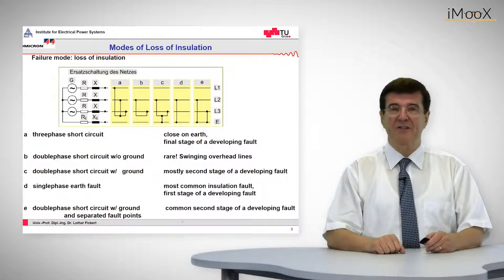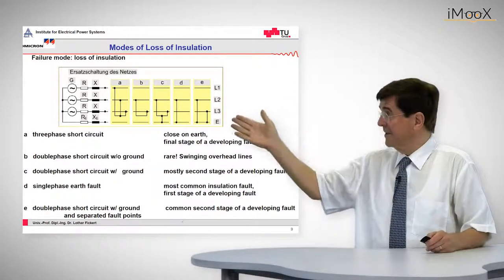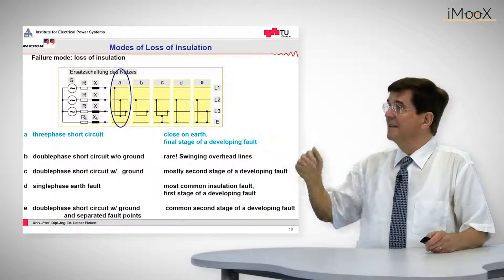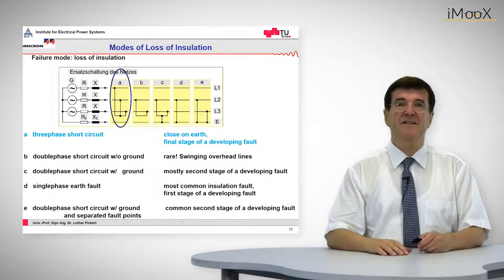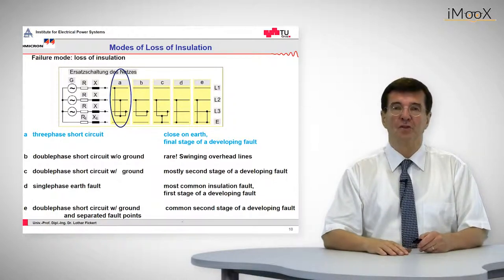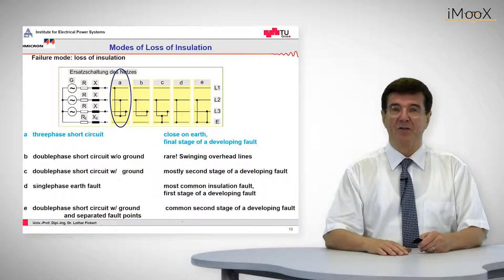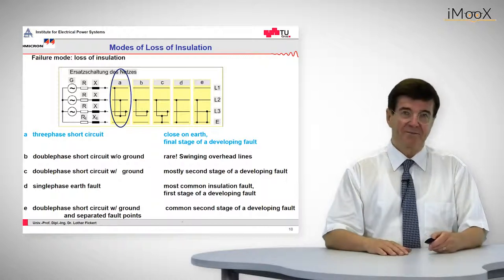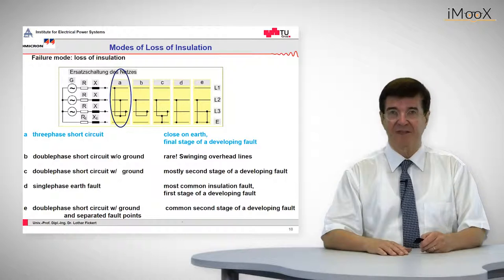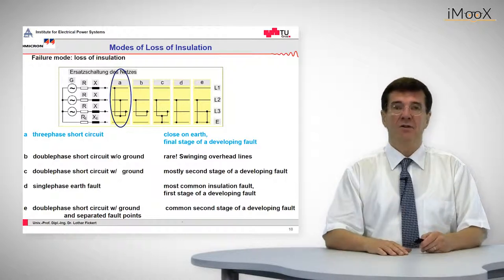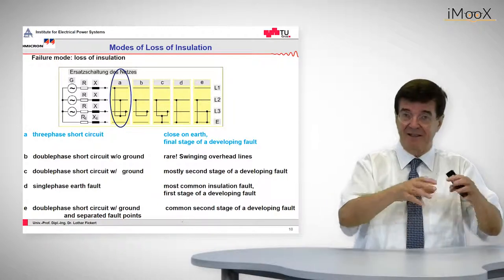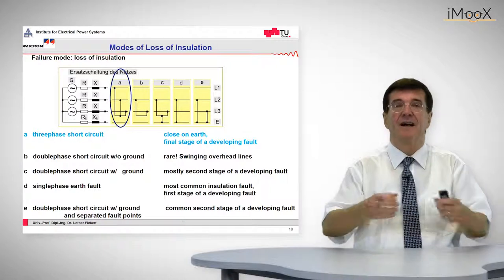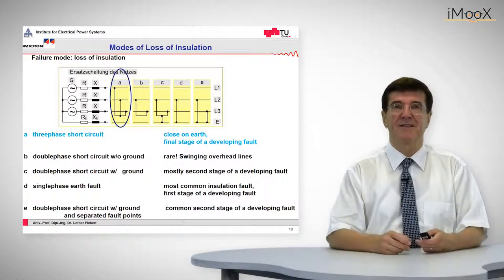The classic classification of these is as we can see to my right side. Let's start with fault class A, which is the three-phase short circuit. This is the easiest one to calculate but in reality it is very rare. Three-phase short circuits normally occur only either by closing on ground — that is a switching error — or at the last stage of a developing fault. A developing fault starts as a single or double-phase fault and the arc burns until the whole thing ends up as a three-phase fault.